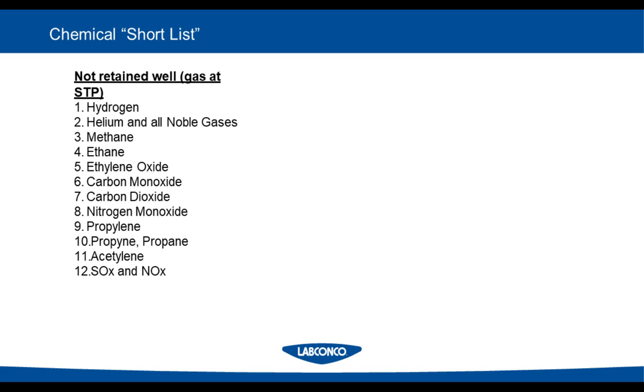So when I talk about the go, no-go, the chemical list, we have 2 different lists. The short list is the no-go list, if you will. These are chemicals that are not retained well by any type of carbon filtration. The best way to look at that is they have low boiling points and low molecular weights. Therefore, they're gaseous at standard temperature and pressure. And this list is basically what you would expect: hydrogen, all the noble gases, methane, ethane, carbon monoxide, carbon dioxide, nitrogen monoxide, you can read SOx, NOx. These are the most common gaseous chemicals.